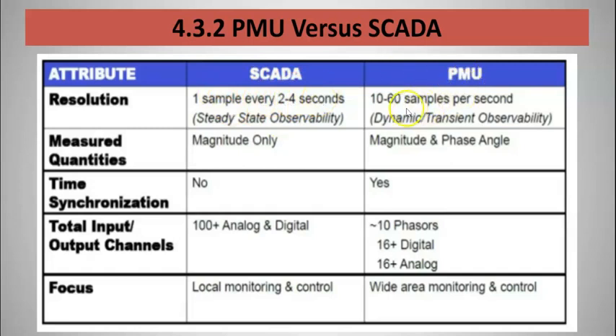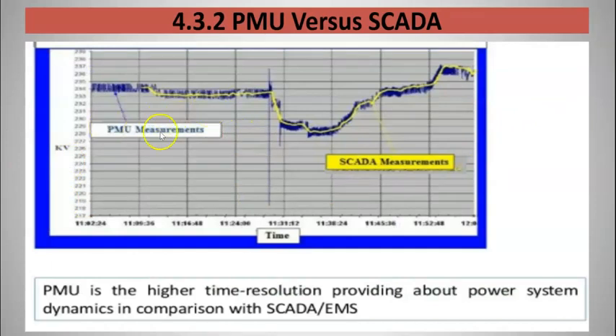PMU gives 10 to 60 samples per second, while the SCADA rate is very low. So if you want to monitor the system, we need very advanced and fast devices. Dynamic transient stability is possible with such advanced technology, while SCADA only gives steady state observability - just magnitude, whereas PMU gives magnitude and phase angle. Time synchronization is not possible in SCADA, but PMU has made it possible. SCADA is generally used for local monitoring in distribution, but PMU is used for distribution as well as transmission systems. You can see the difference between PMU and SCADA in terms of measurement and resolution.